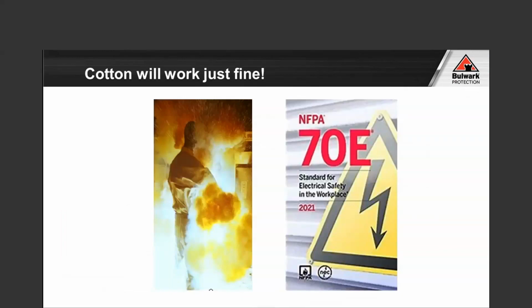On our electrical front, cotton works just fine. Believe it or not, as far and as deep as we are into NFPA 70E, the fact that we're 21 years into when the actual standard first came out talking about flame resistant garments when doing energized tasks, we still have pockets where cotton is fine for my electricians because it's a safety upgrade. It will not melt or drip. The part that they fail to talk about is up until the point it ignites. Once it ignites, it's definitely contributing to injury.